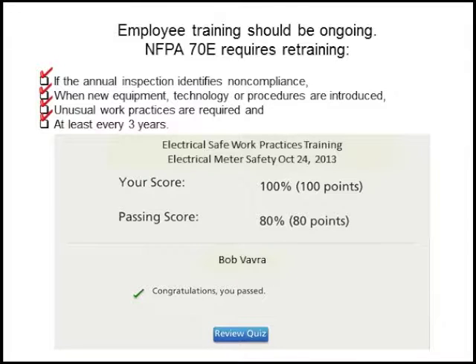Employee training should be an ongoing process. The NFPA requires that we do training if the annual inspection identifies there's some issues of noncompliance, anytime new equipment, technology, or procedures are brought into the workplace, or if we're doing any unusual work practices. It states very clearly in the standard that any job you haven't done within the last 12 months needs to be considered new work. And we need to review their training at least every 3 years.